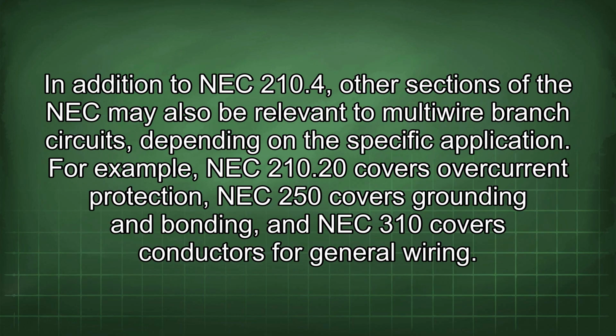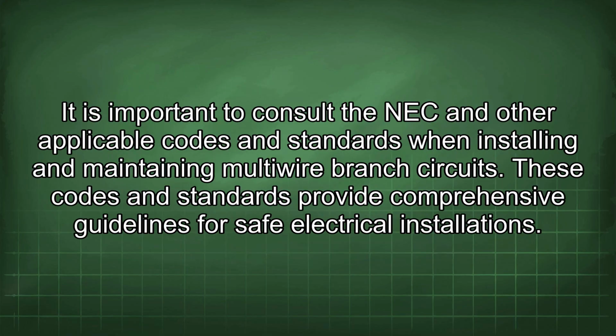In addition to NEC 210.4, other sections of the NEC may also be relevant to multi-wire branch circuits, depending on the specific application. For example, NEC 210.20 covers overcurrent protection, NEC 250 covers grounding and bonding, and NEC 310 covers conductors for general wiring. It is important to consult the NEC and other applicable codes and standards when installing and maintaining multi-wire branch circuits. These codes and standards provide comprehensive guidelines for safe electrical installations.